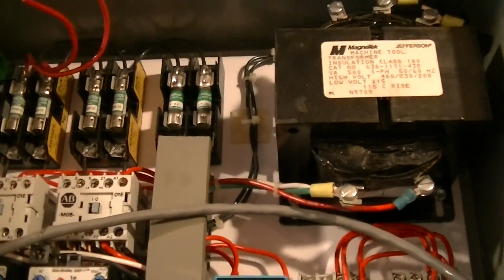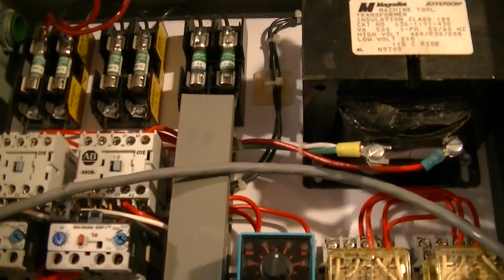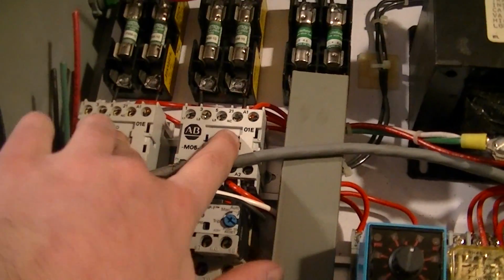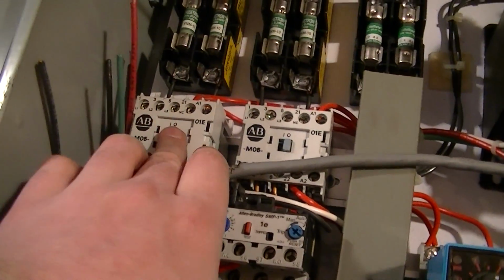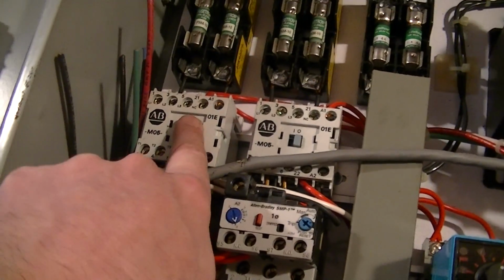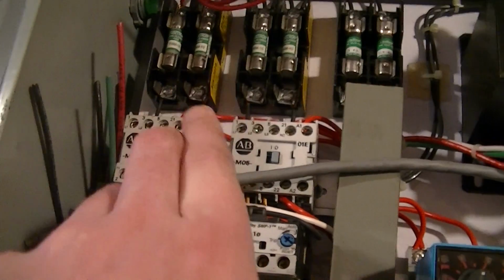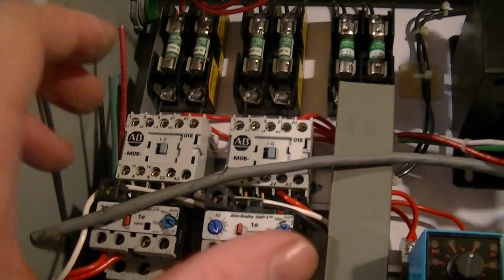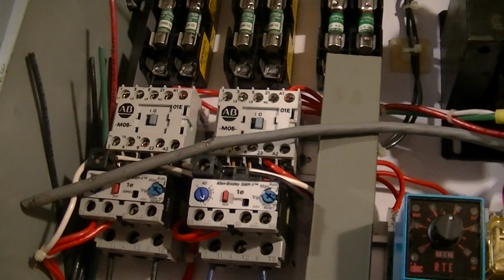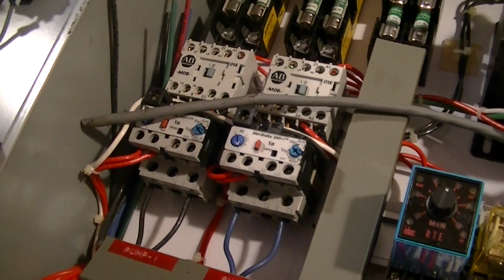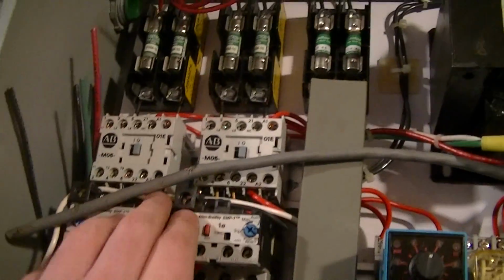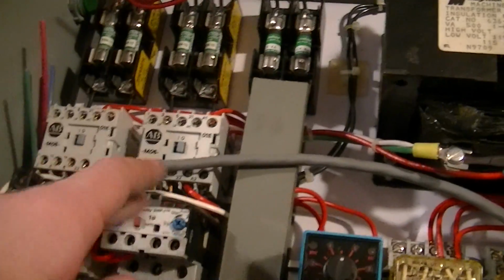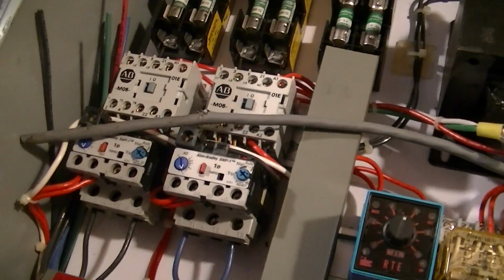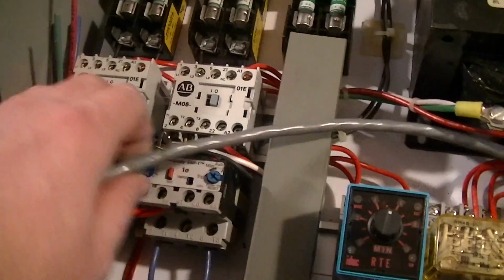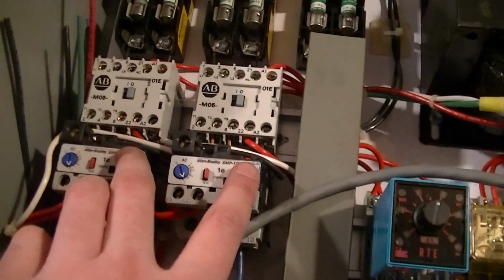Of course, the difference between a control transformer and a conventional power transformer is that a control transformer is intended for dealing with loads where you have a really high inrush, predominantly contactors, because mechanically inside the contactor, the assembly that the coil pulls in, before it actually pulls in and completes the magnetic circuit, the inductance of the coil is much lower, and thus the operating current is much higher, because the relations for inductance are much like the relations for resistance. Basically, it's an inverse proportionality as far as the inductance versus the current and power, blah blah, just basic AC circuit schmoo.